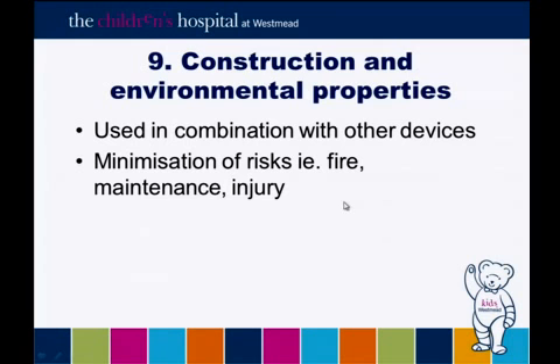The construction and environmental properties: most devices may be used with other devices. If I've got a ventilator measuring your thoracic volume using Alistair's newfound impedance technique, which they're starting to release commercially, and that's interfering with your normal ECG machine, then that's a problem. So we do have that problem.